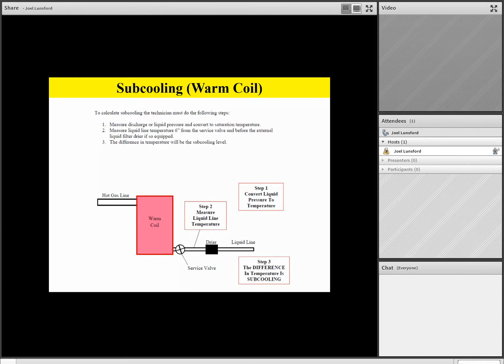So let's talk about how to calculate subcooling at this time. So step number 1, we're going to convert our liquid pressure or our discharge pressure in our example. They're essentially going to be the same. So liquid pressure or discharge pressure we convert to temperature off of our pressure temperature chart. Step number 2, we clamp on our temperature probe and we physically measure the temperature of the liquid line leaving the warm coil. Step number 3, we find the difference between those two temperatures, and the difference is our subcooling level.